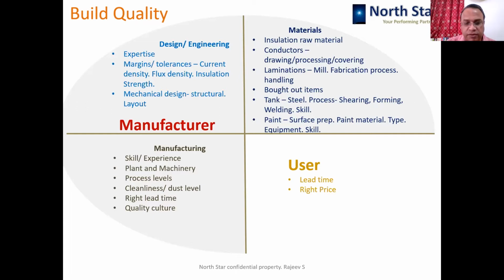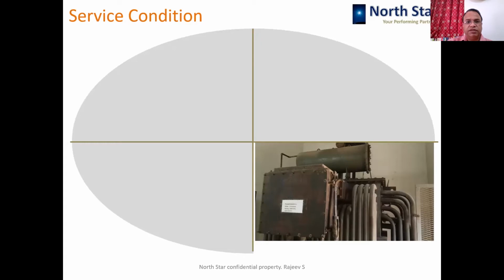See, this point looks very, very mundane, but as you must be aware, normally there is a lot of delivery pressure when the transformers are coming, especially when it is a project like an EPC project, where deliveries are very tight. So when you are not giving sufficient lead time to the transformer manufacturer, the transformer quality may get affected. And then the right price. Of course, I'll not go into that aspect because price is a decision-making point, at least in our country, and a lot of emphasis is given on the lowest price. That also indirectly affects the transformer quality. Service condition is the second performance factor.